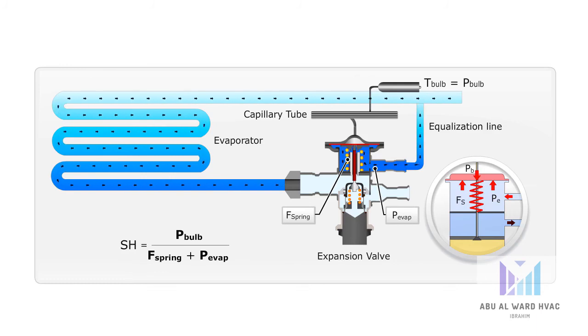If the load on the evaporator decreases, the decreasing superheat will in turn decrease the bulb temperature or pressure. This will close the TXV orifice so less refrigerant is injected.